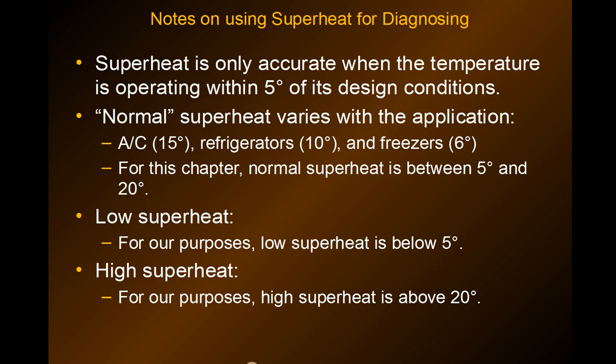This is really important: superheat is only accurate when the system is operating within five degrees of its design conditions.